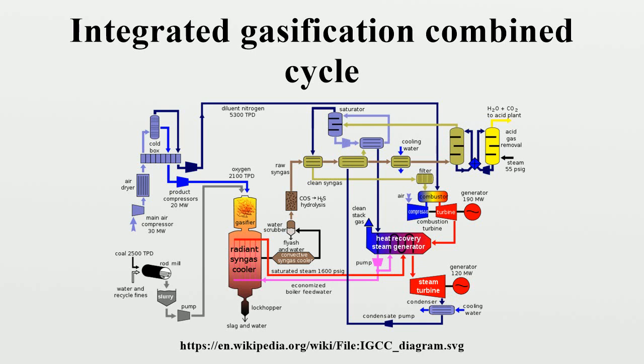It employs not only F-type turbines but G-type as well. Next-generation IGCC plants with CO2 capture technology will be expected to have higher thermal efficiency and to hold the cost down because of simplified systems compared to conventional IGCC. The main feature is that instead of using oxygen and nitrogen to gasify coal, they use oxygen and CO2.